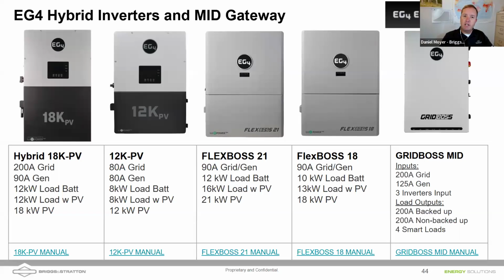What EG4 did is, instead of having 200 amp pass through in and out and the ability to shut that on and off, they took that and put it over here in the GridBoss. And they kept the charge controllers over here. They got rid of the gen port over here, and they kept it all on this side. So essentially all the FlexBoss is doing is acting as the charge controller, an inverter and a battery charger, so that we're positioning this close to the battery wherever it may be in the house, and then simply running AC between the FlexBoss and the GridBoss.